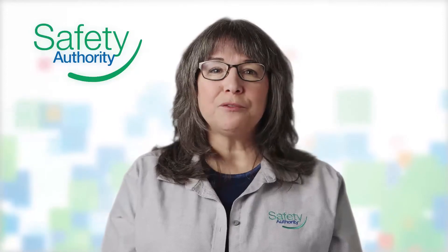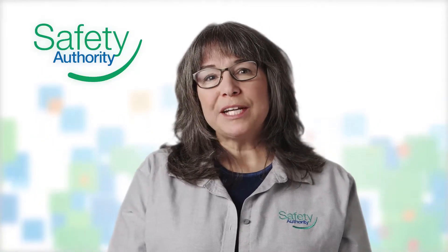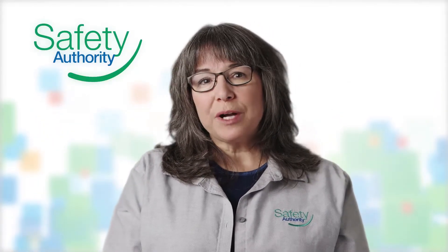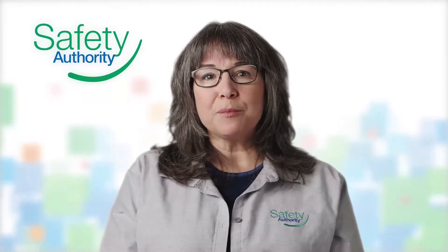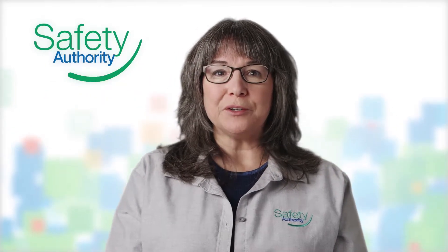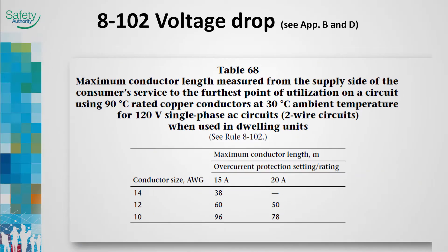This new sub rule and voltage drop table provides users with a quick reference to determine the maximum circuit length for dwelling units. Table 68 can be applied when the total length of the branched circuit or feeder is measured from the supply side of the consumer service to the farthest point of utilization in a general lighting or receptacle circuit. Where the installation does not lend itself to using Table 68, voltage drop calculations should be performed using Sub Rule 1.